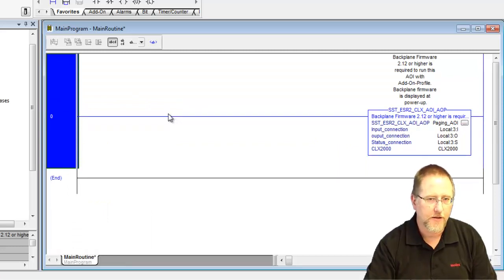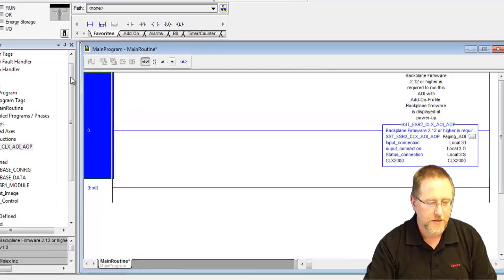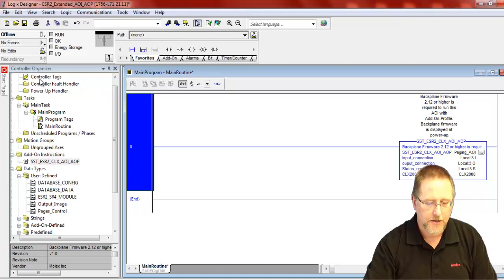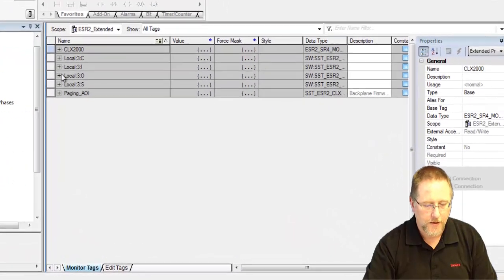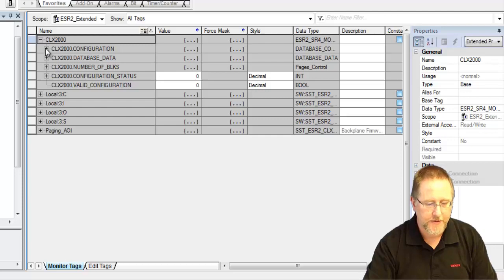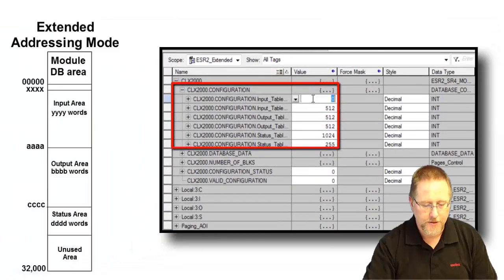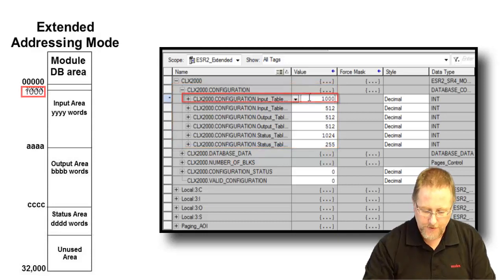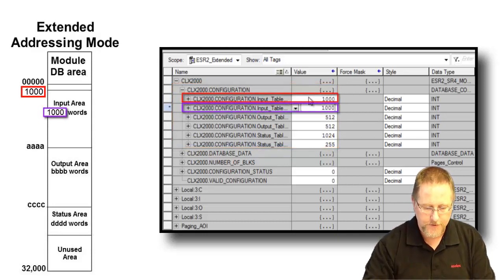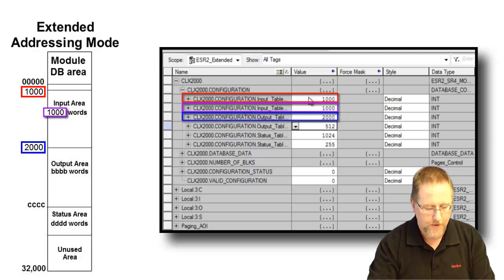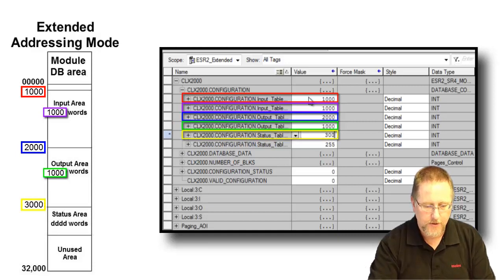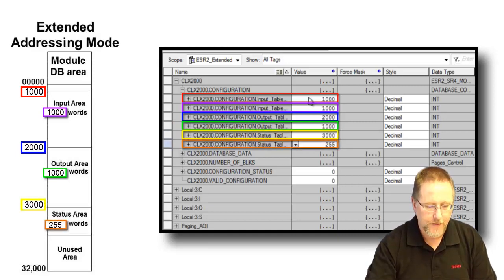We went into the database in the console and set up the offset for our input and output tables and the links for input and output tables. So we go up to the controller tags, and we expand the CLX 2000, and we go to the CLX 2000 configuration, and we want to change the input table offset to 1000, and the length was also 1000. And we started our output table at 2000 and length of 1000, and we started our status table at offset 3000 with length 255.